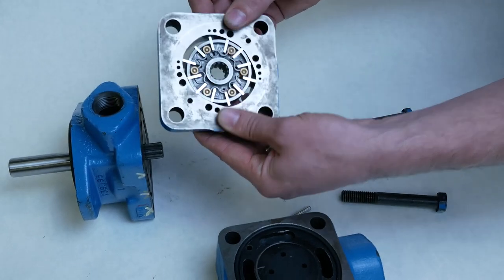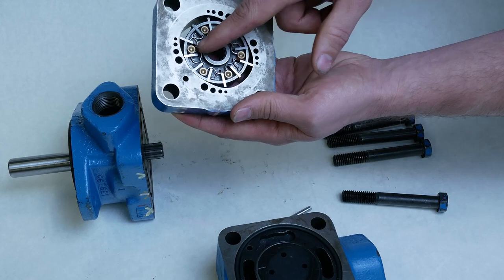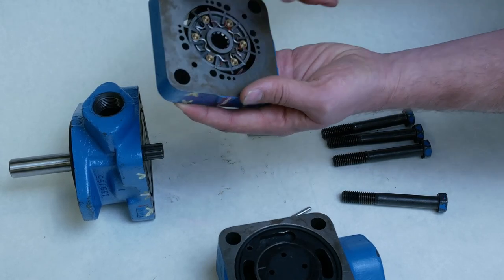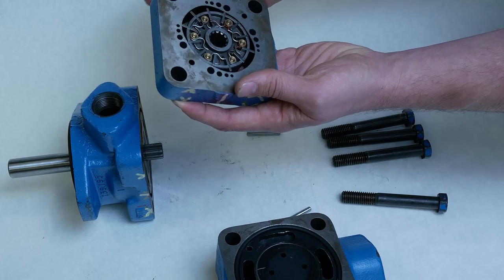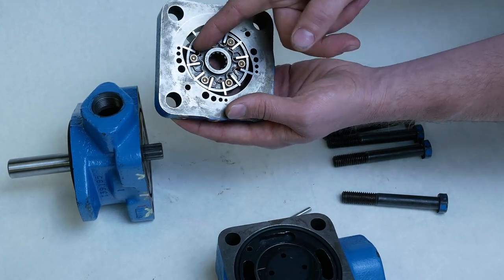As is common with our vane motors, we see that each vane is spring loaded to be able to push out. Some of these springs have been popped off, and so I should and will, before I reassemble it, reset these springs.